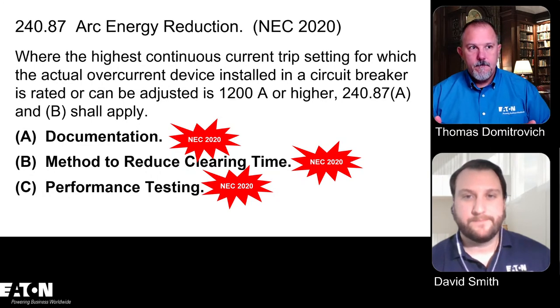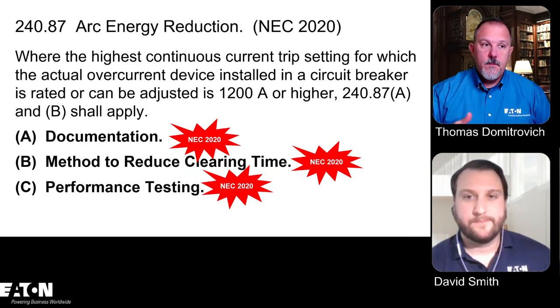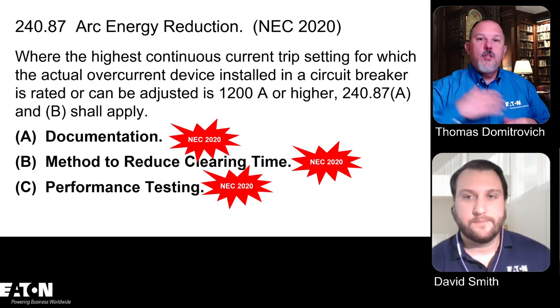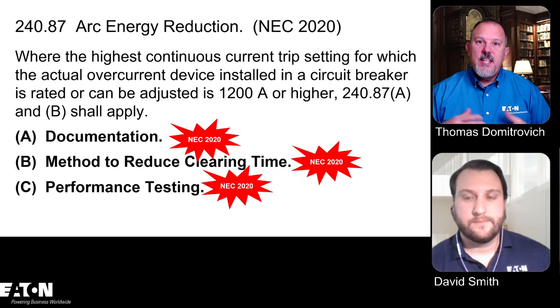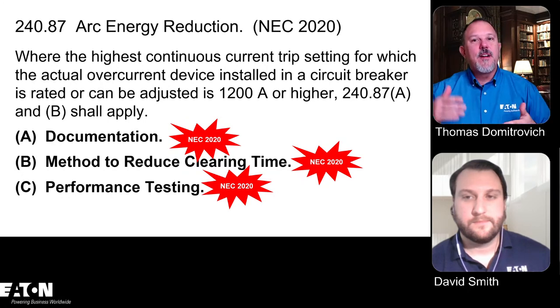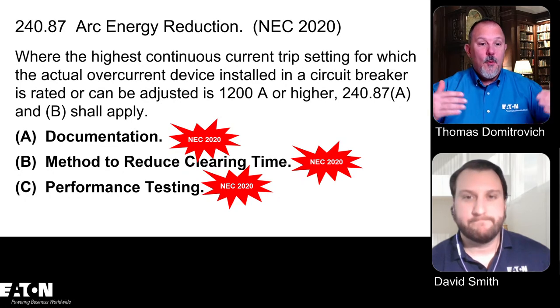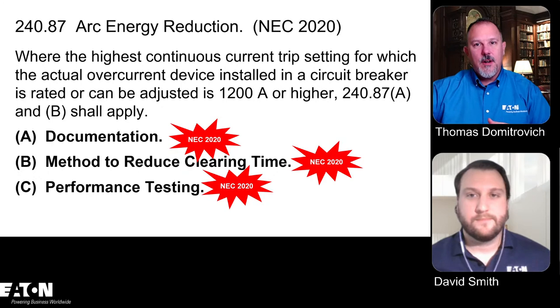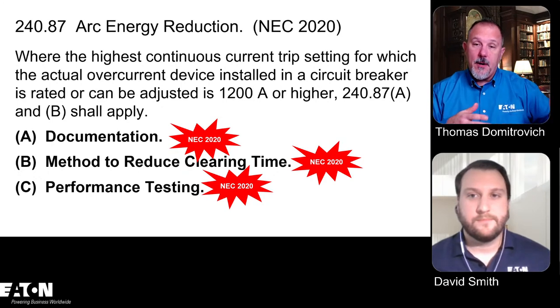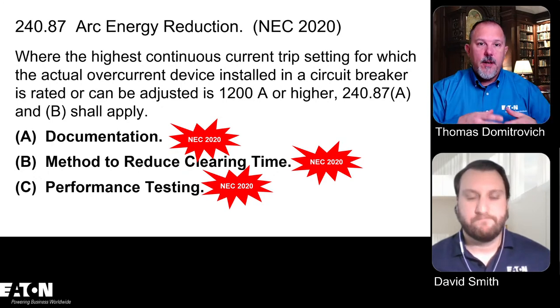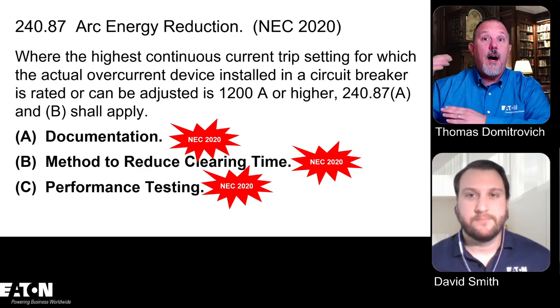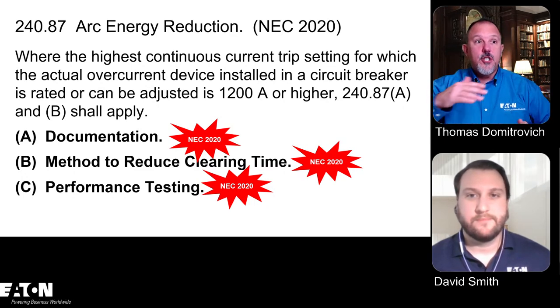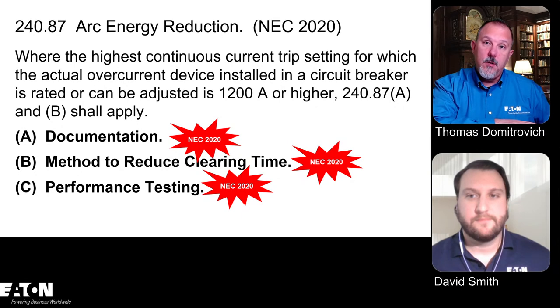Yep. Now, what you'll notice is that in 208 volt systems, typically my available fault currents are high, right? Like on a transformer, the secondary of a transformer, my fault currents are higher than on the primary because the primary has a higher voltage. So as my voltages go down, my currents go up. And as my voltages go up, my currents will go down, right?